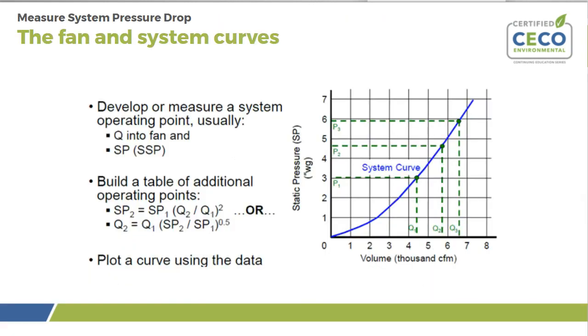Fan curves: the fan manufacturers have a lab or a setup area where they mount a fan to a pedestal, hook it up to the drive, and record. They'll set a speed, induce static pressure, and get the correlating system volume at those points, plot them as dots and connect the dots. Then they do it for multiple speeds, so that when you see a fan multi-rating table, it is a collection of those static pressure and volumetric points for multiple selections.